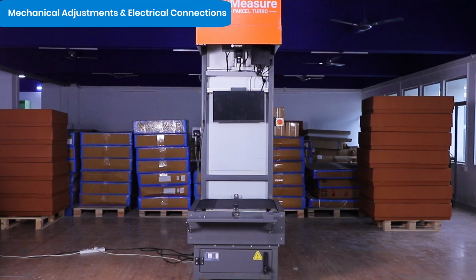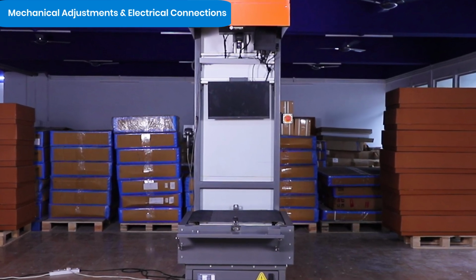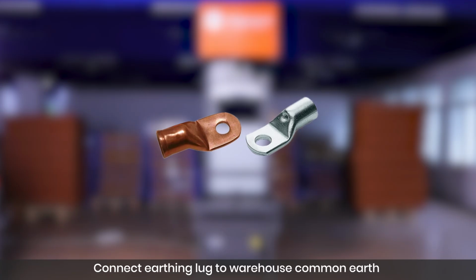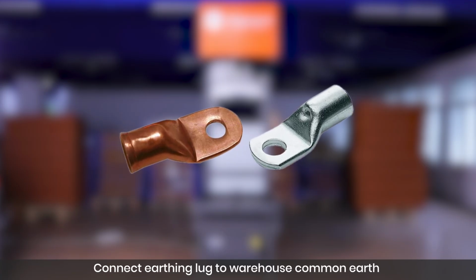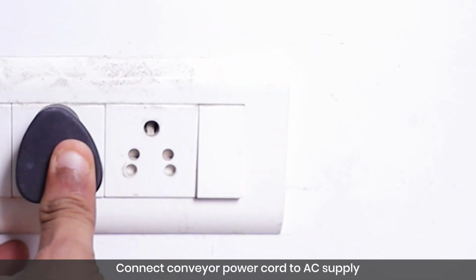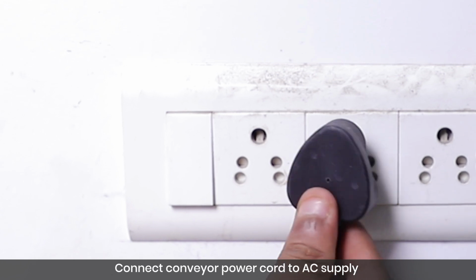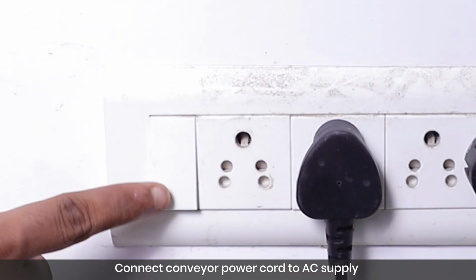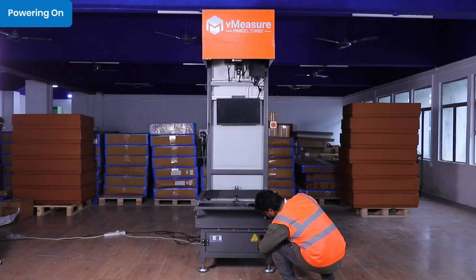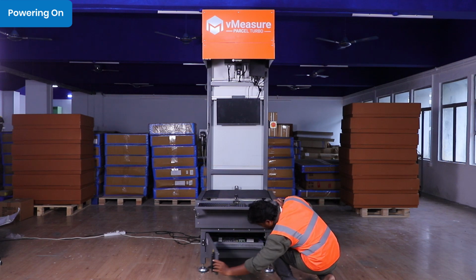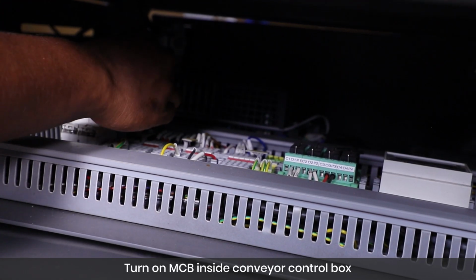Now, let's move on to the overall setup's mechanical adjustments and electrical connections. At the back side of the setup, connect the earthing lug to the warehouse's common earthing point. You'll also find 2 power cords, one for the conveyor and one for the dimensioner. Connect both to the warehouse AC supply. Once the voltage readings are confirmed, open the conveyor control box and turn on the MCB to power the conveyor.